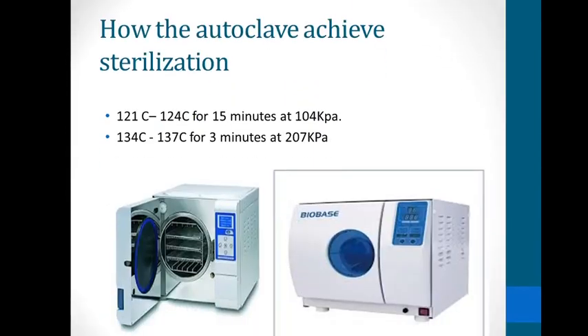Here is how the autoclave achieves sterilization. If we adjust the autoclave at 121 to 124 degrees Celsius, it will be kept working for 15 minutes. So the instruments will be placed inside the autoclave for 15 minutes.